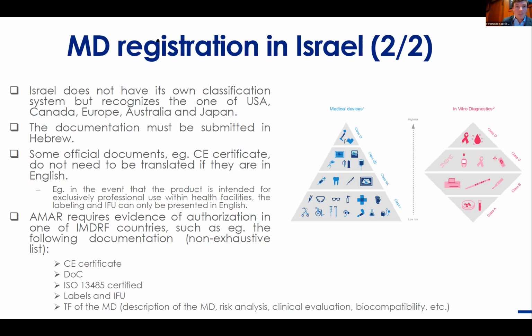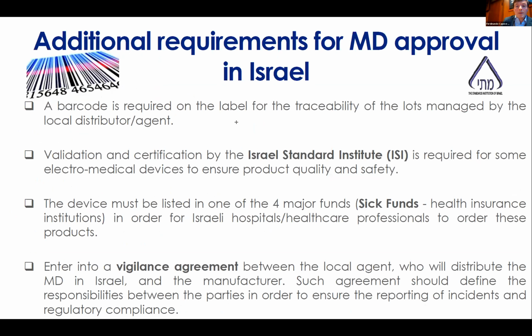There are some additional requirements for devices that apply to Israel: a barcode for the traceability of the lot, approval from the Israeli Standards Institute for some electromedical devices, the requirement that the device be listed in one of the four major funds, the Sick Funds, and a vigilance agreement between the local agent and the manufacturer, defining responsibility between the parties to ensure prompt reporting of incidents and regulatory compliance.